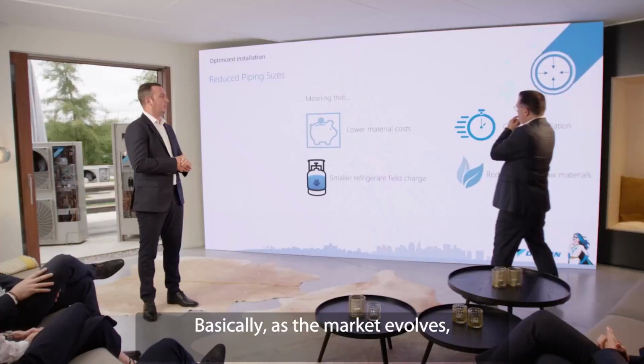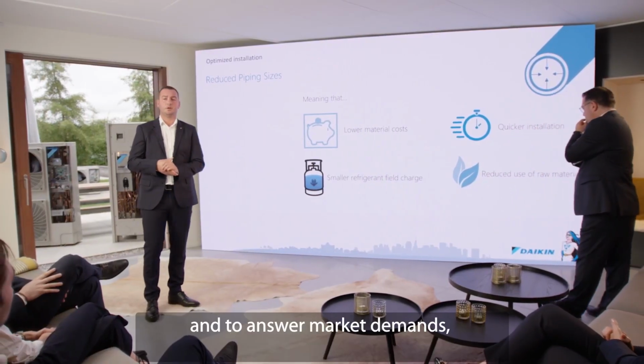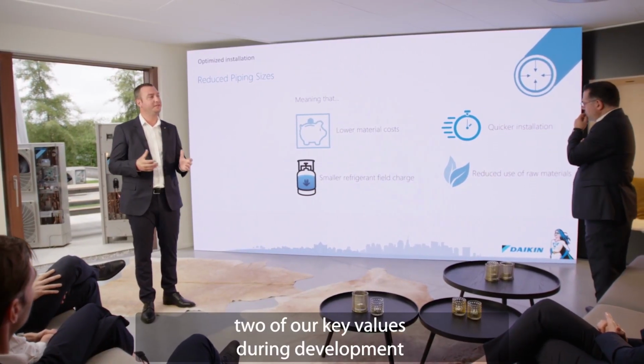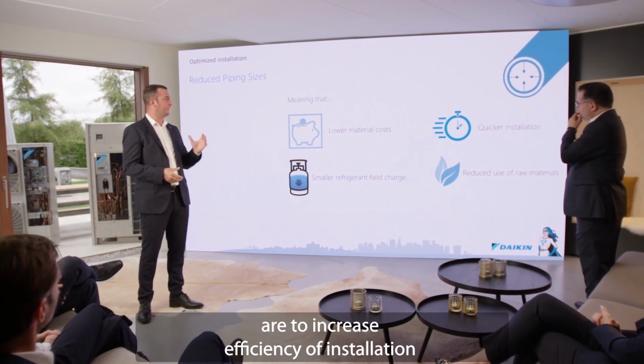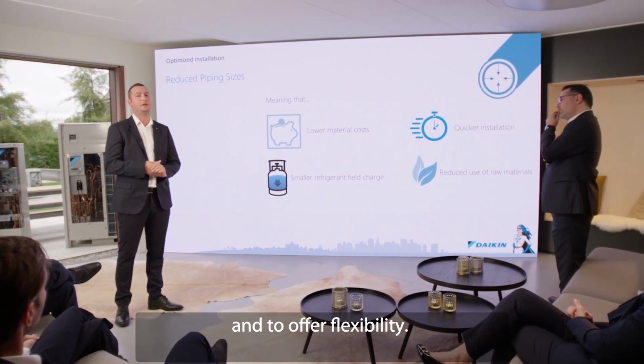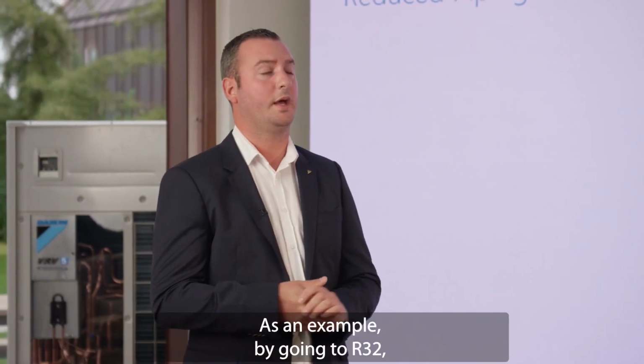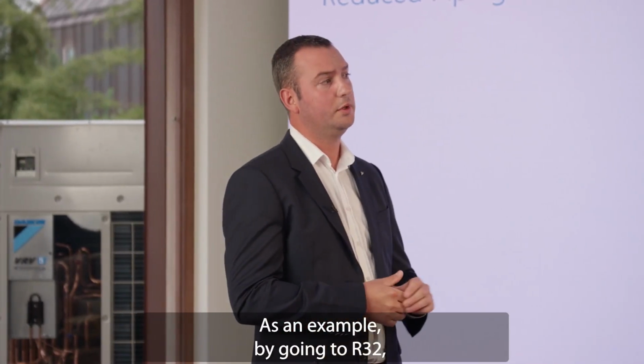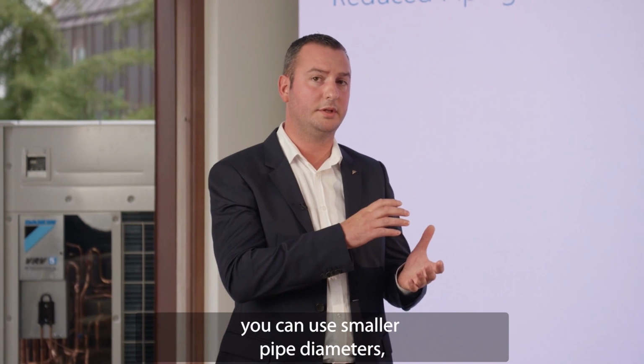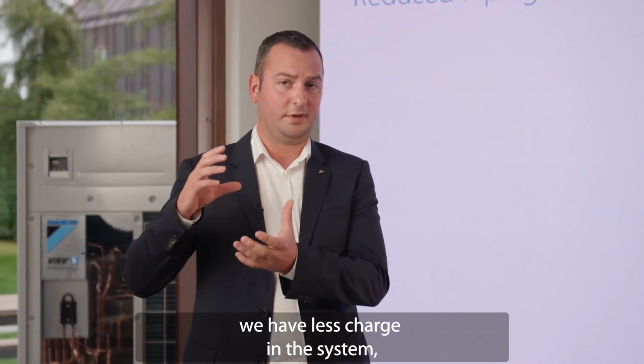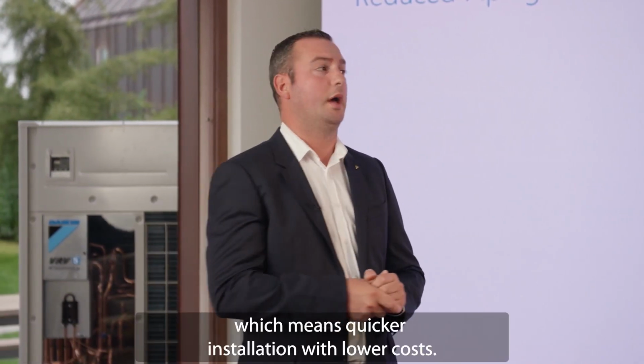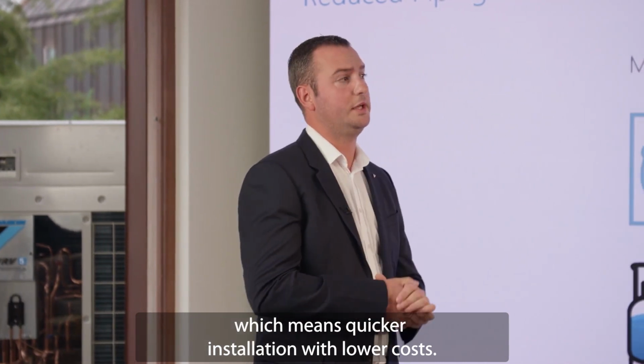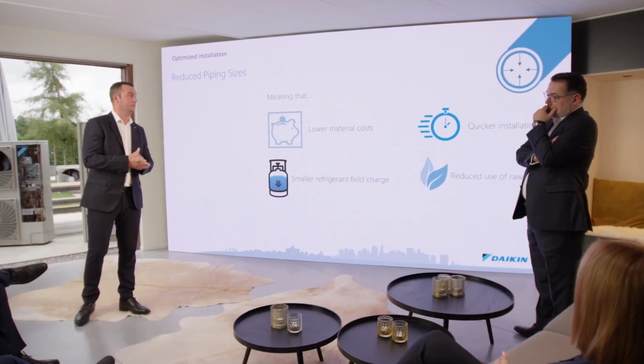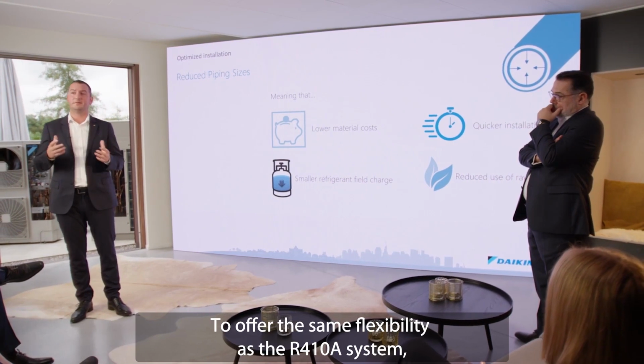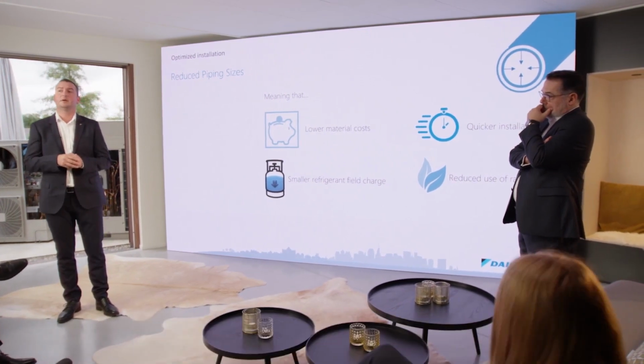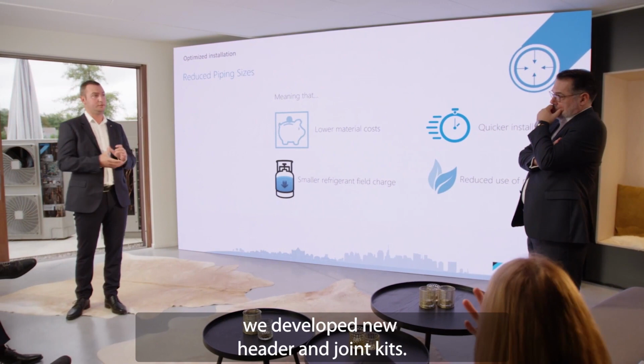Basically, as the market is evolving and to answer market demands, 2 of our key values during development are to increase the efficiency of our installation and to offer flexibility. As an example, by going to R32, we can use smaller piping diameters and have less charge in the system, which means a quicker installation and lower installation cost. Next to this, to offer the same flexibility as the R410A system, we developed new header and joint kits.